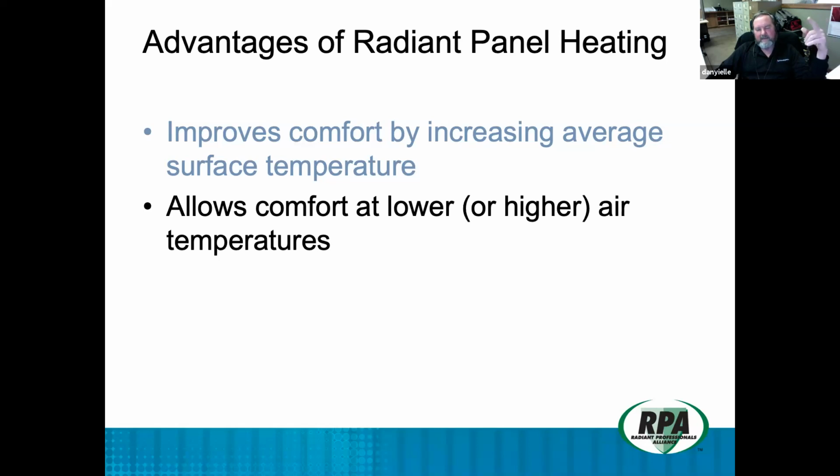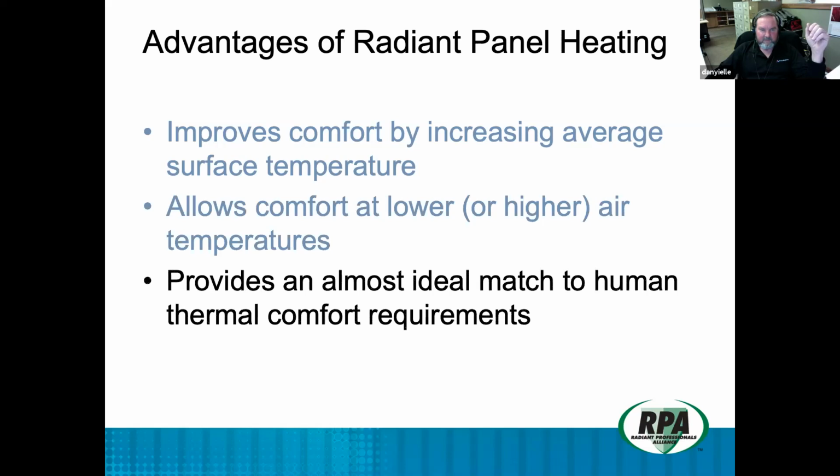And if you go to Robert Bean's website, he's actually a member of ASHRAE and was a key person in developing a program that essentially calculates what the mean radiant temperature will be for any given circumstance. And if you get into a situation where it's not going to be comfortable, it will tell you, and then you can tell the consumer, hey, I can't guarantee your comfort because of this, and my recommendation would be that you go to triple pane windows instead of double pane so that we raise that surface temperature and lessen the possibility of you feeling uncomfortable.